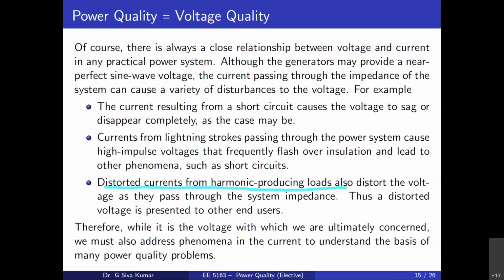Distorted currents from harmonic producing loads also distort the voltage as they pass through the system impedance. Thus, a distorted voltage is presented to other end users also. Therefore, while it is the voltage with which we are ultimately concerned, we must also address the phenomena in the current to understand the basics of many power quality problems.